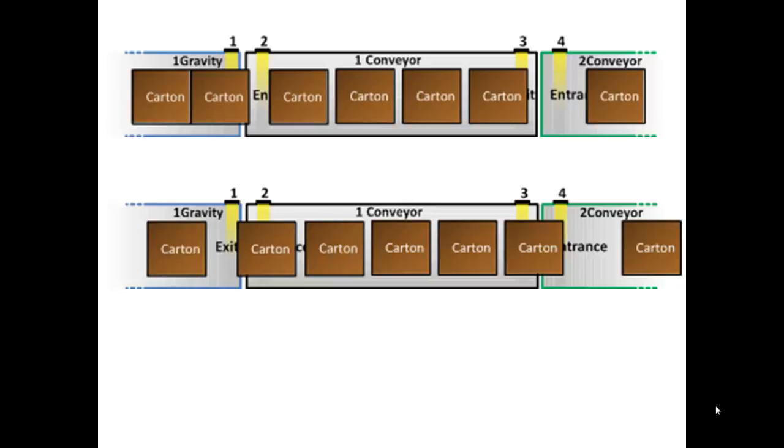We purposefully singulated the cartons on one conveyor by controlling the logic in such a way that one conveyor pulls one off at a speed faster than the next carton can fall by gravity, and so the carton that is being pulled onto one conveyor just clears photo eye 2, and one conveyor stops before the carton can get down against the leading edge of one conveyor.